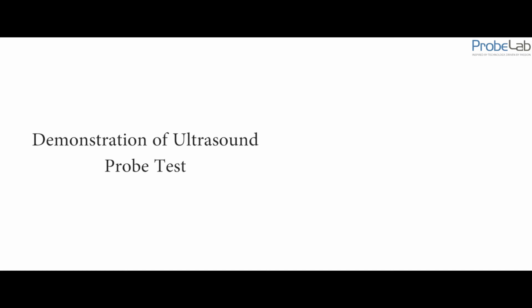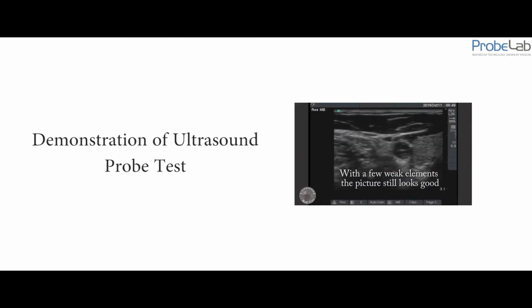Now this basic test should be performed anytime you take a machine either out of storage or probe out of storage. It might be that probe that you never use if you had multiple probes on your POCUS machine, or anytime you take a new purchase of equipment. It could be new equipment, it could be refurbished equipment. You want to check it out and see what you got. Now as you saw, we had some weak elements there, but that on this particular machine doesn't make much of an imaging quality issue for me for the type of exams I perform.